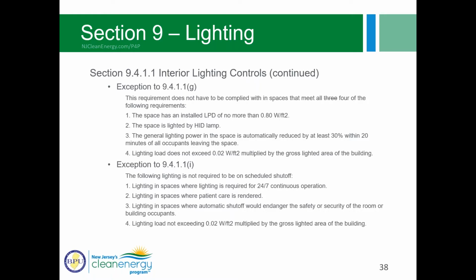Here, item G applies to automatic partial off and full off controls. The general lighting power in the space shall be automatically reduced by at least 50% within 20 minutes of the occupants leaving that space. And if you notice in that first line, where it says this requirement does not have to be complied with in spaces that meet all four of the following requirements, in the 2016 language it actually says 3, but it lists 4 exceptions. I caught this when I was looking through and thought, oh, this might be a typo. Sure enough, in the 2019 version of the code they have revised it to say 4. So I have revised it here to say 4 as well, because you have to comply with all 4 of those things for the exception to apply.